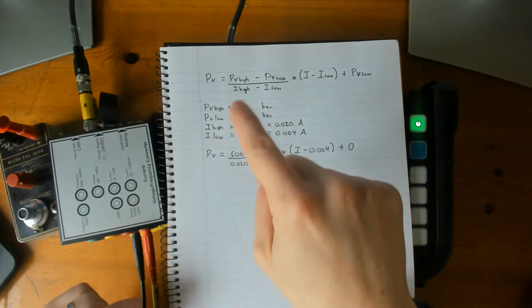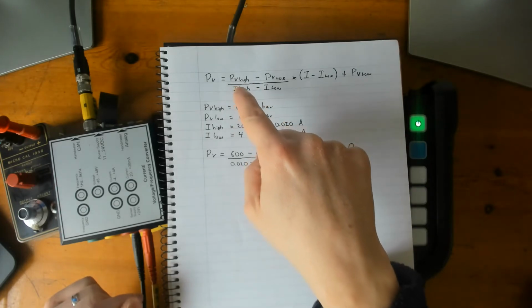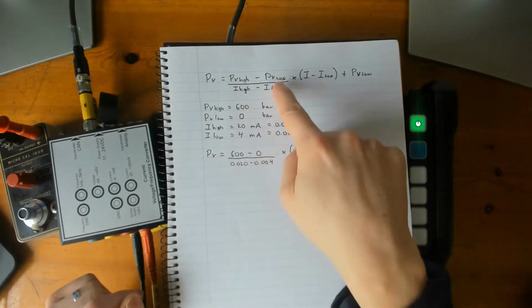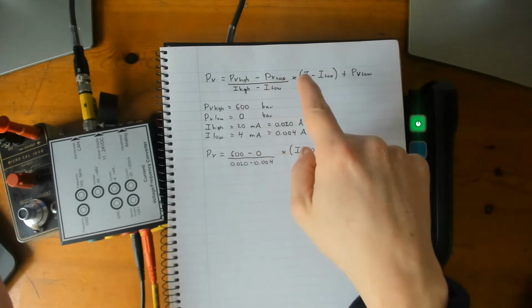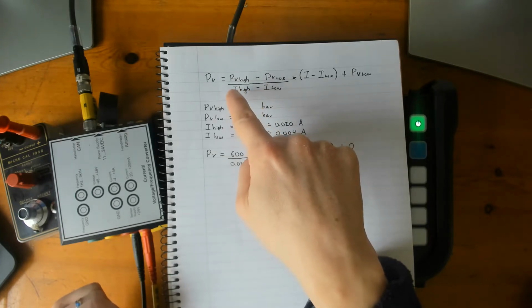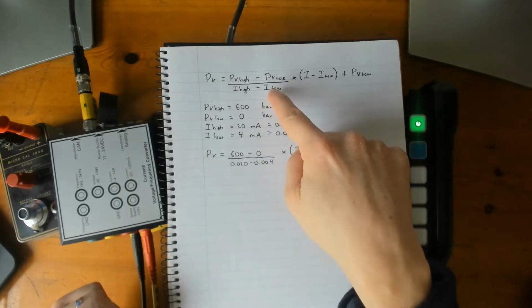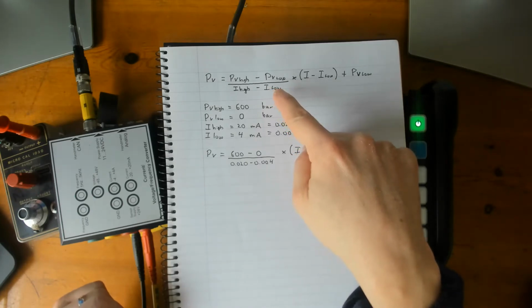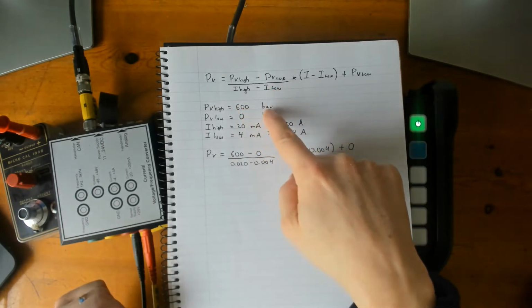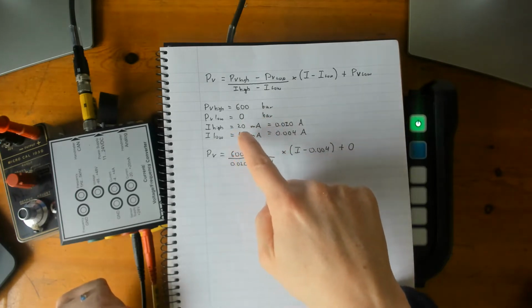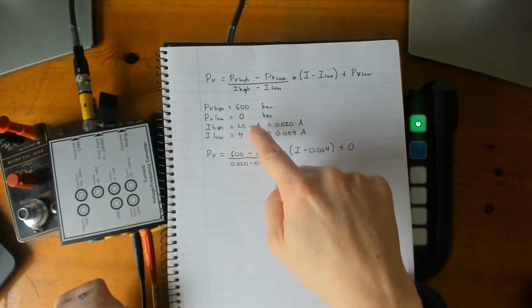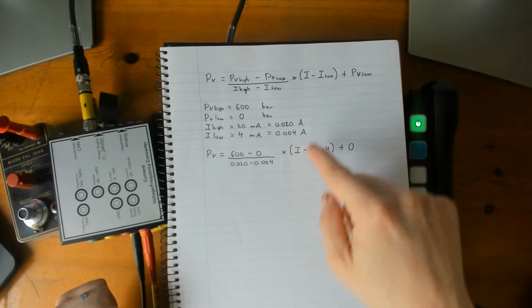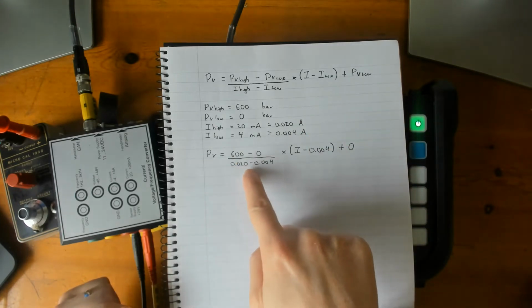So this will be my maximum value of the sensor that I want to connect. In this case, I'm going to pretend that it's a 600 bar transducer. And this will be the lower value, which will be 0 bars. This will be the maximum current, which is going to be 20 milliamp. And this one is going to be the low current, which is going to be 4 milliamps. So I already put that here. And I need to put those values of current not in milliamp but in amps, so I have to convert that into amps. So my equation will look like this.